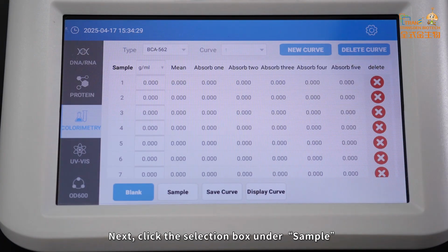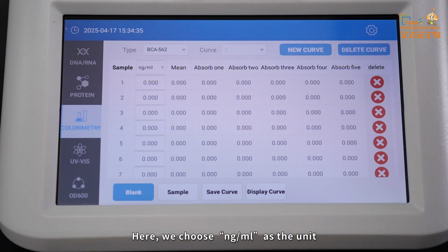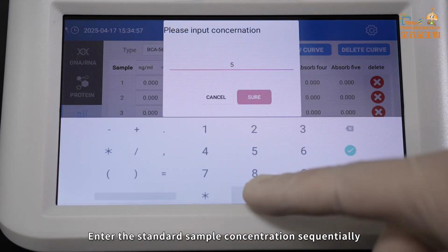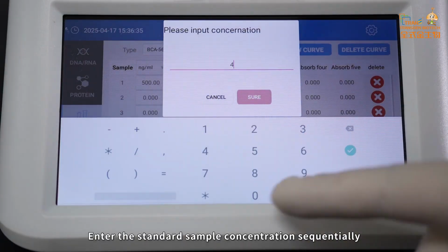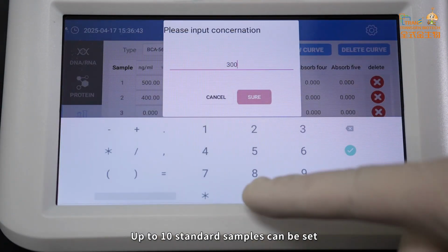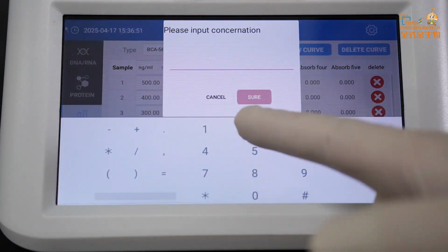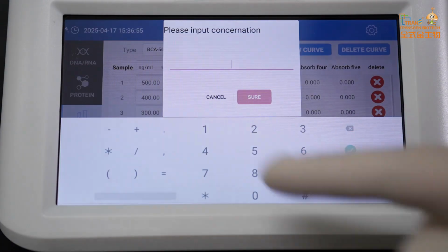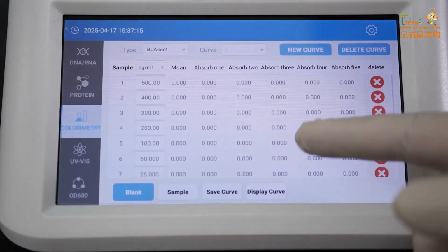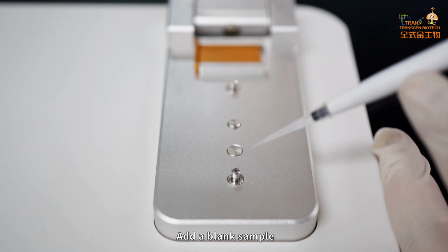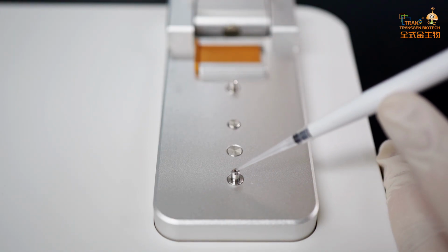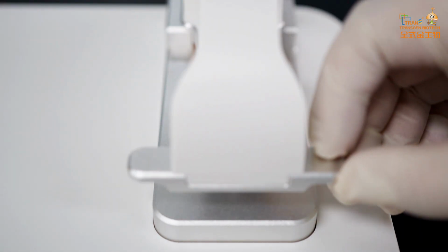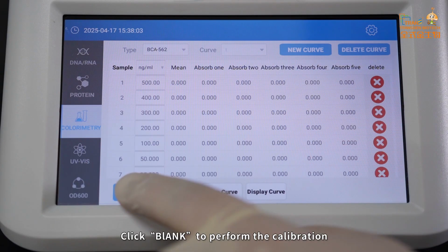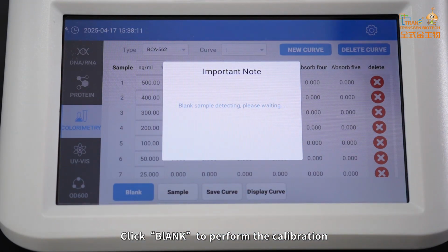Next, click the selection box under Sample. Here, we chose nanogram per milliliter as the unit. Enter the standard sample concentration sequentially. Up to 10 standard samples can be set. Add a blank sample. Click Blank to perform the calibration.